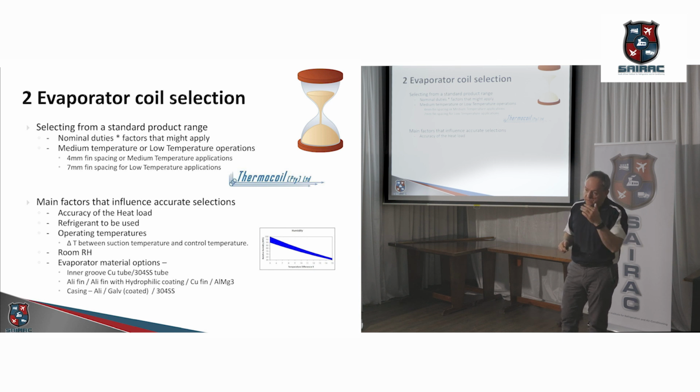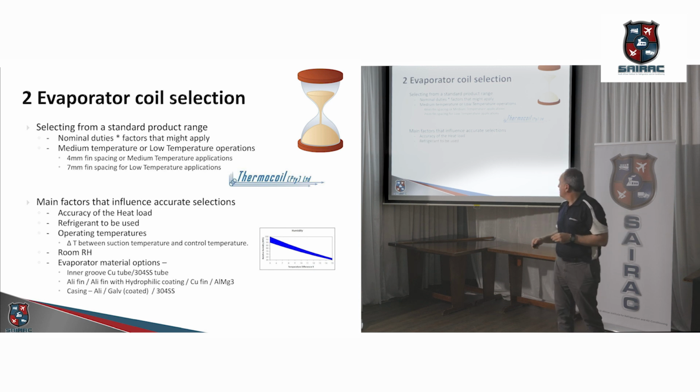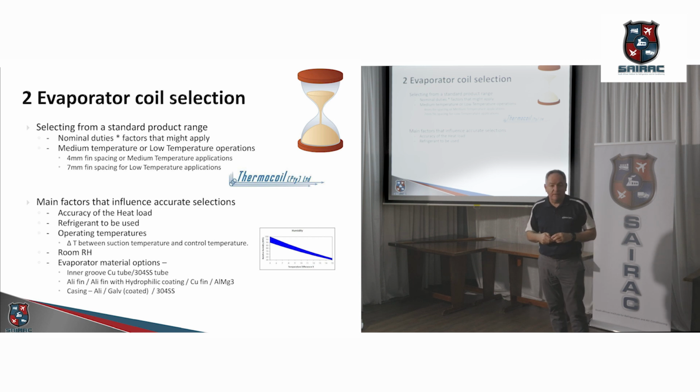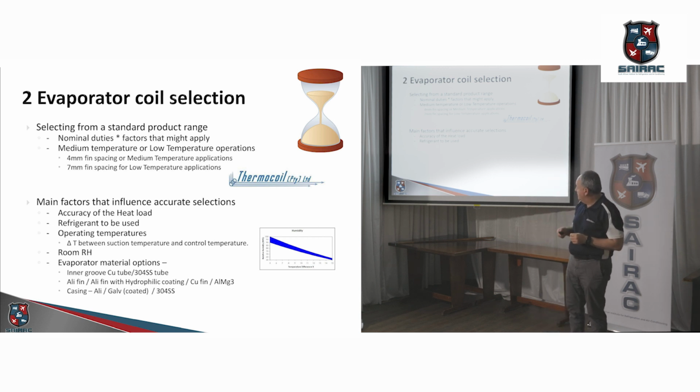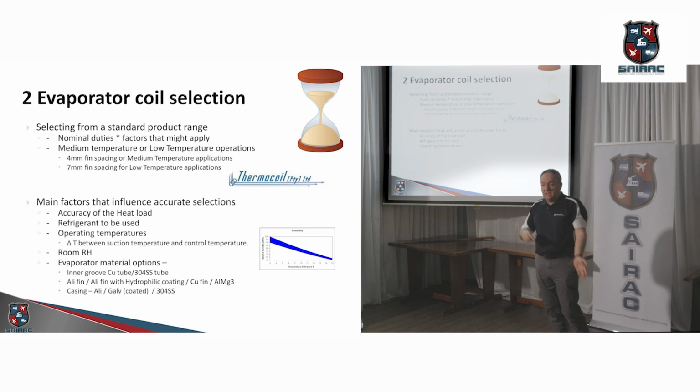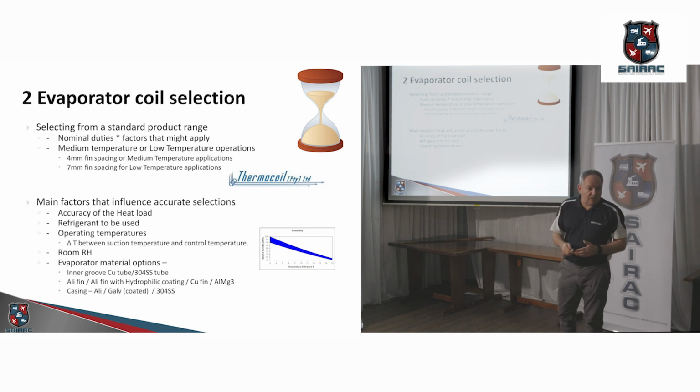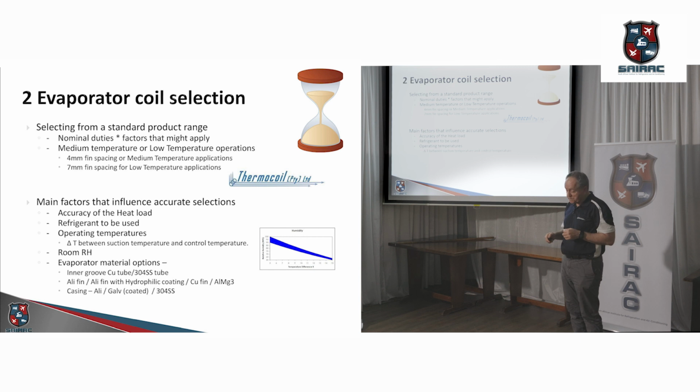It's really useful to see how well your plans worked out. And of course, the refrigerant that you're using. Sometimes I get someone that's looking for an evaporator, and they want to connect it to a split aircon unit that they salvaged from someplace. So the refrigerant very much affects the duty of the evaporator. Then operating temperatures. Is it a freezer room that they sometimes want to turn into a cold room? It's really bizarre what some people do sometimes, but obviously your operating temperatures are crucial.